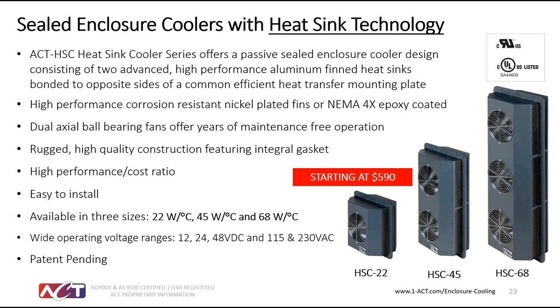Our sealed enclosure cooler technology is available in three different sizes for the heat sink coolers. And the way the industry typically rates these devices, it looks at a 20-degree spread or delta between the inside cabinet temperature to the outside cabinet temperature. So like the HSC22 has a thermal conductance of 22, which means that for 1 degree C rise, you get 22 watts of cooling. So what you would do is take that 20-degree rating times 22, and you would get 440 watts of cooling with a 20-degree C temperature differential between the inside to the outside of the enclosure. So just a quick way to see how those devices work.